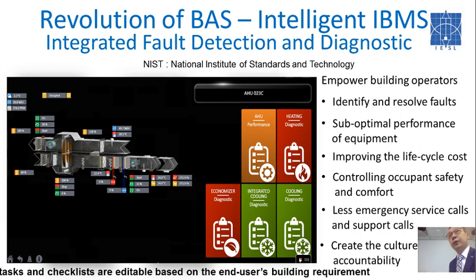I like this the best—the reason is that building owners, technicians, and engineers create accountability. Before IFDD in BMS systems, operators just commanded start-stop, changed schedules, changed set points, and viewed and monitored trends. That's about it—look at it, no alarms, everything is good. With IFDD in place, any abnormality within the equipment triggers a warning, and engineers and technicians will learn from it. If I'm a new technician or engineer hired by an owner, I may not know what to do, but with the checklist, technicians and engineers learn and improve their skill set. That's why it creates a culture of accountability.